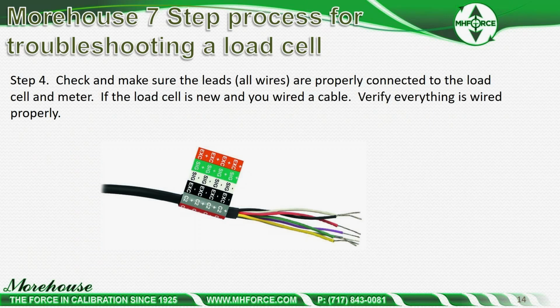Step 4, check and make sure the leads, all wires, are properly connected to the load cell meter. If the load cell is new and you wired a cable, verify everything is wired properly. It's real easy to switch wires, especially when you don't have the colors right. We've seen numerous cells come in with typically red as positive excitation, black negative. The other day we saw someone have blue and black. So it's good to double check. You can use a multimeter and verify the pinouts.